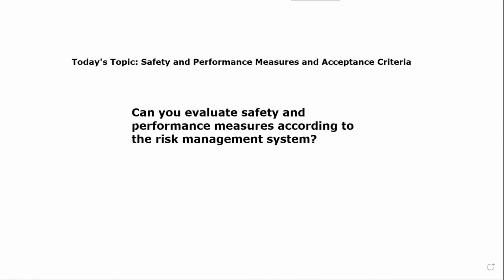So I'll start off by saying that this is an excellent question. Sarah and I were reviewing this question before the call started, because we're not often asked how the safety and performance assessment, the assessment of subject device data using the lens of safety and performance acceptance criteria, relates back at the end of the day to the risk management system, the risk and benefit profile of the device. That's really where, in our opinion, the final arguments of the safety and performance of the device live, in the risk benefit section of the CER or the PER for that matter.